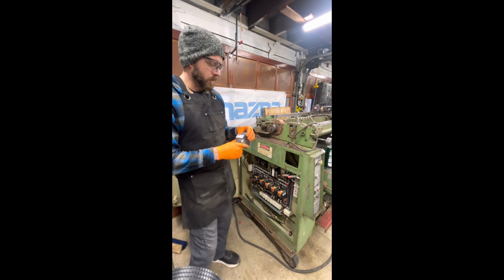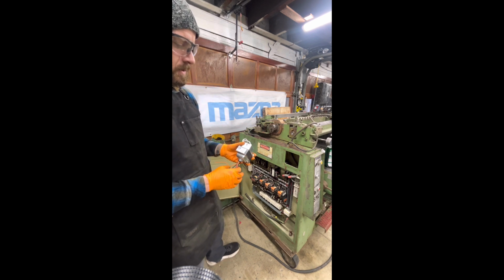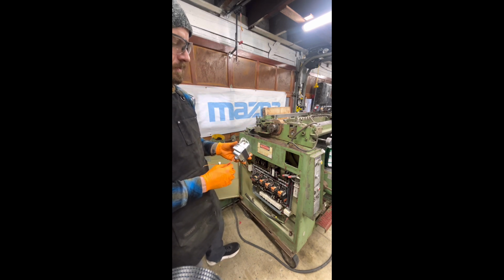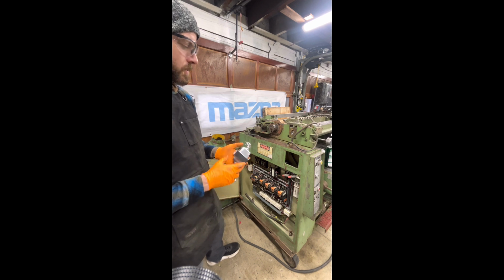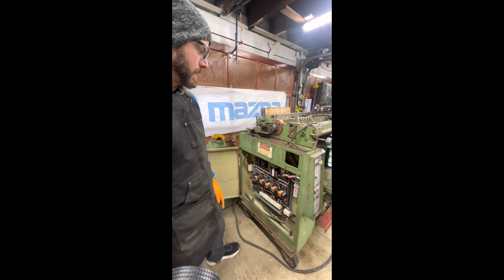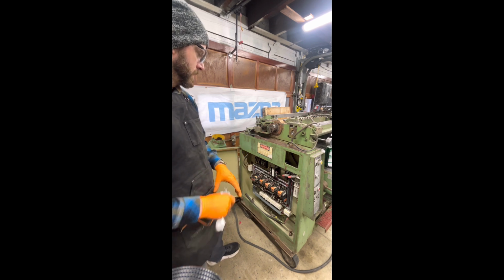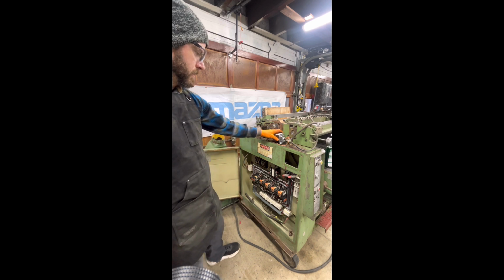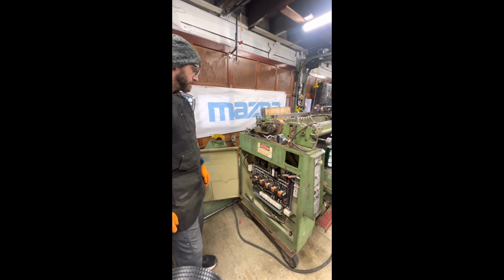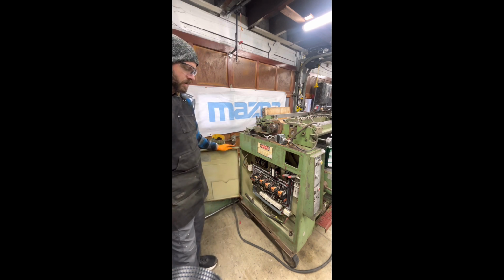Here you can see the transformer that I have pulled out of the unit. This is just a standard step-down transformer that would be for like 208, 480, whatever you need to drop the voltage down. This could work, however, it's just not the correct style for it. And I had this control circuit one laying around that I ended up putting in. The box had a fair bit of dust in it just from them having the door propped open to have that plug-in 120 volt power for the start and stop buttons.